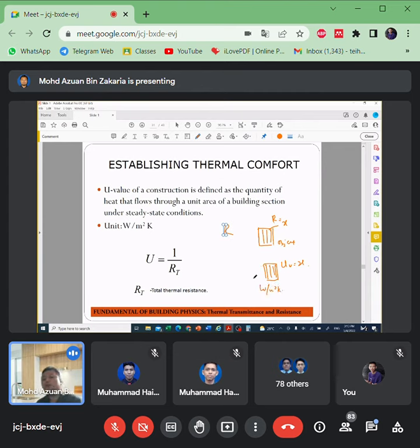How many watts can transfer? For example, a U value of 5 means 5 watts can be transferred through the single material or through the layers of material. Meanwhile, R value says that material or that combination will create an R value of 5, resistance of 5 meter squared Kelvin per watt. But U value is a different perspective of explanation.